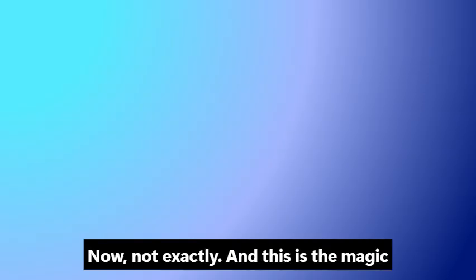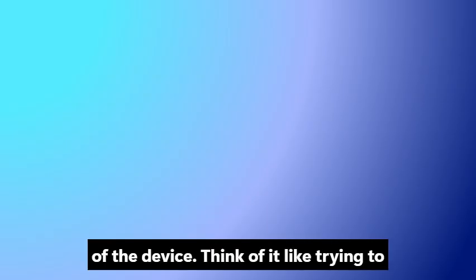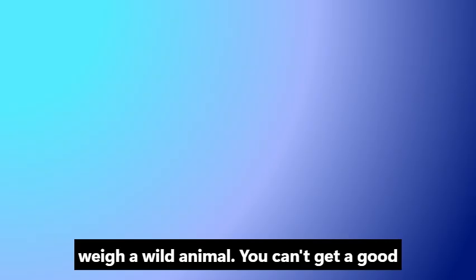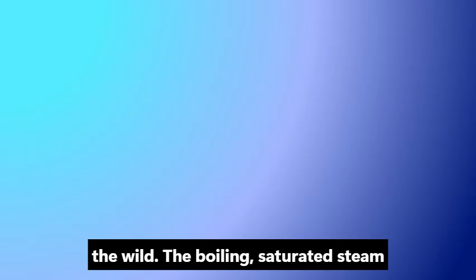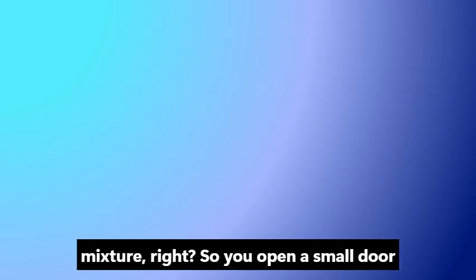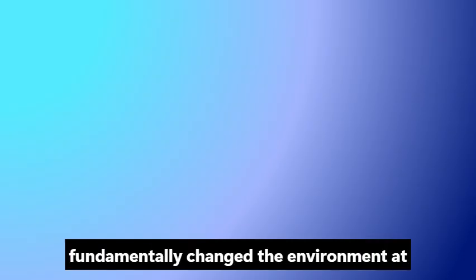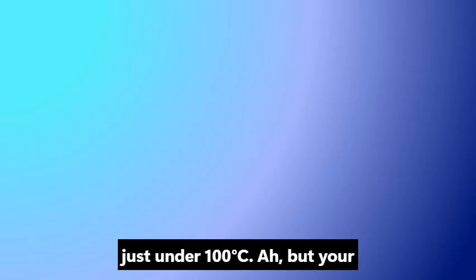You still have steam, it's just at a lower pressure now. Not exactly. And this is the magic of the device. Think of it like trying to weigh a wild animal. You can't get a good reading while it's thrashing around in the wild. The boiling, saturated steam mixture. Right. So you open a small door and let it run into a controlled cage where it calms down. By dropping the pressure to 100 kilopascals, we fundamentally change the environment. At that low pressure, water boils at just under 100 degrees Celsius.